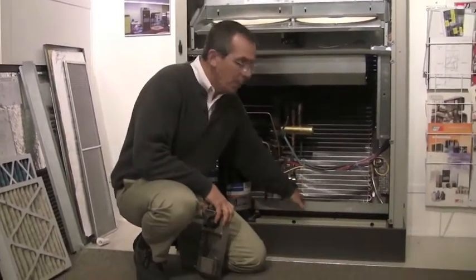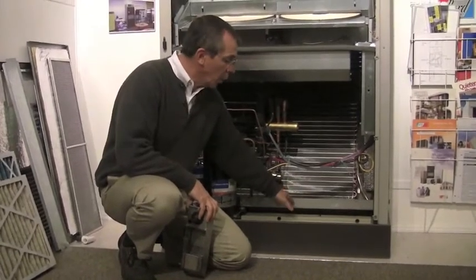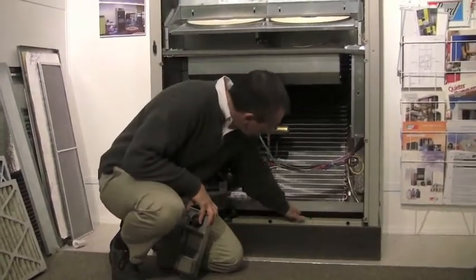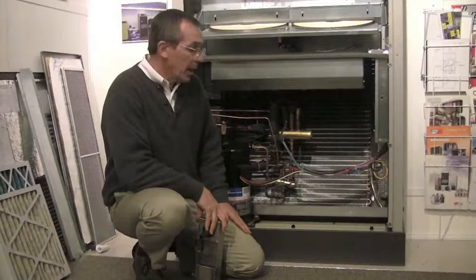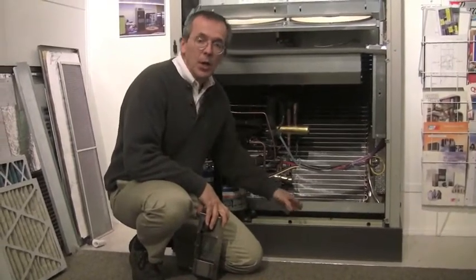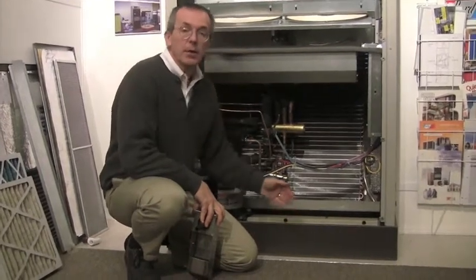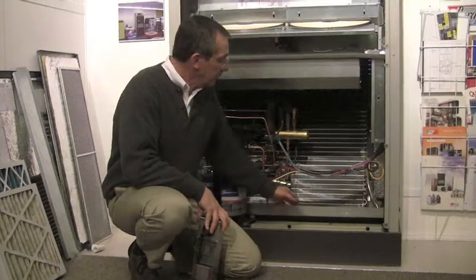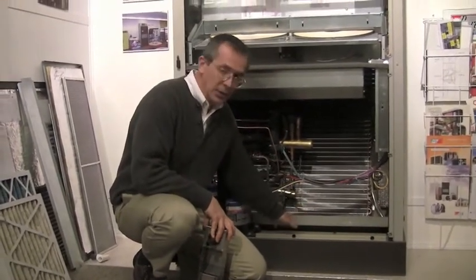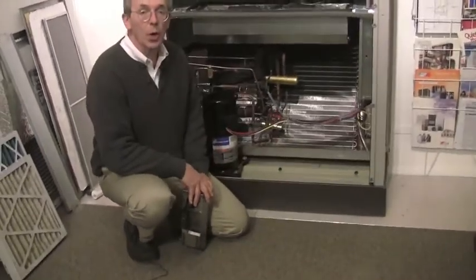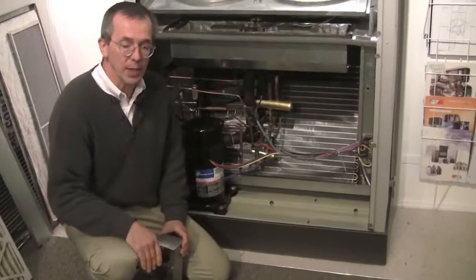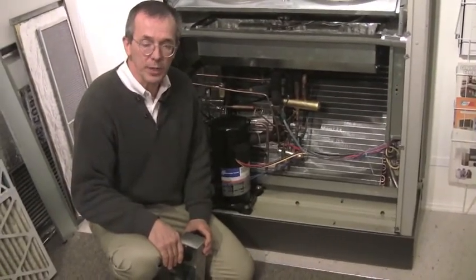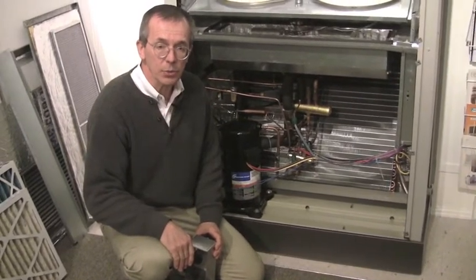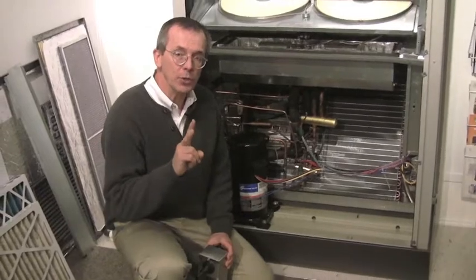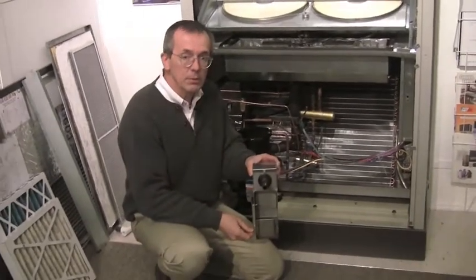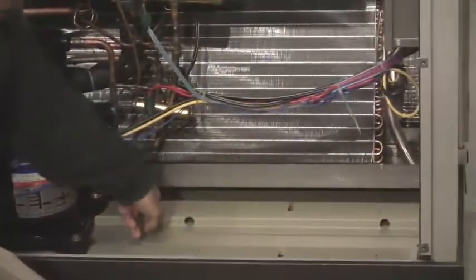For some reason, if this whole pan stops up and the water runs over into the base of the unit, it has 3 emergency drain holes here in the bottom underneath the condensate pan. The wall sleeve comes beyond those holes. So once again, if water comes into the base of the unit and into the emergency drain holes, the water is going to go into the wall sleeve, and once again the wall sleeve is going to take the water to the outside and run down the side of the building, indicating you've got an issue with the drain system.